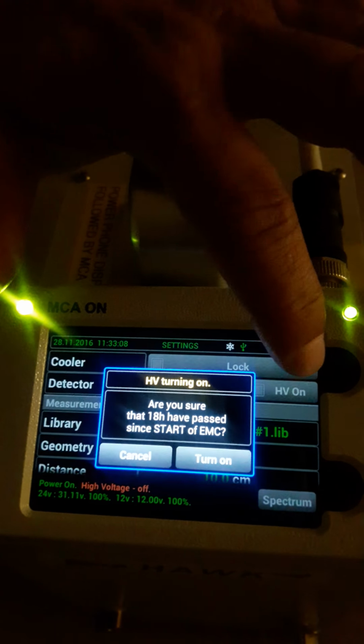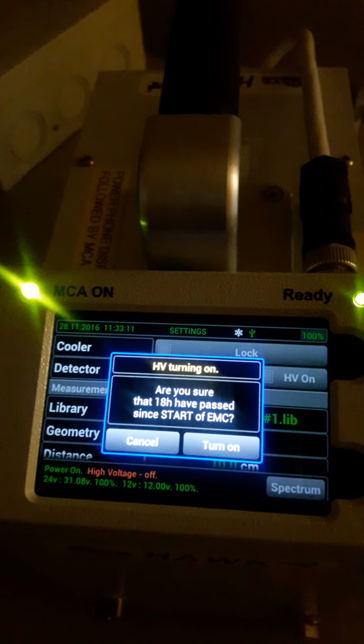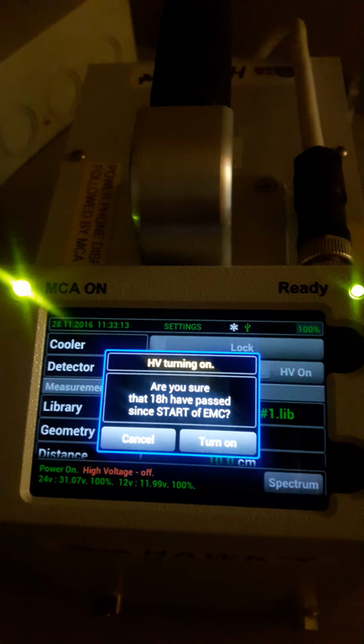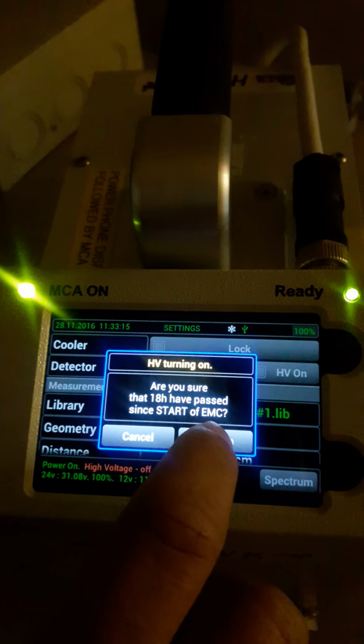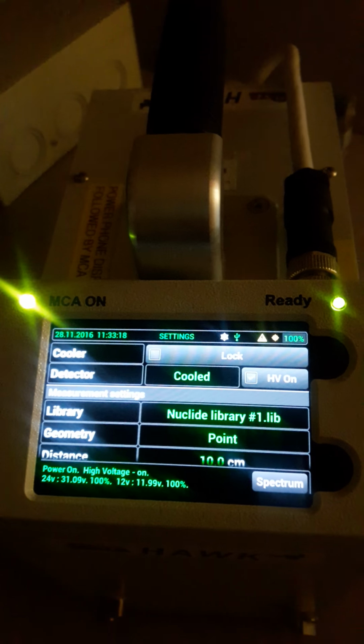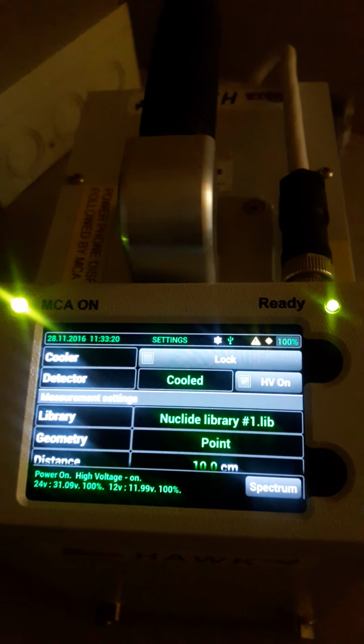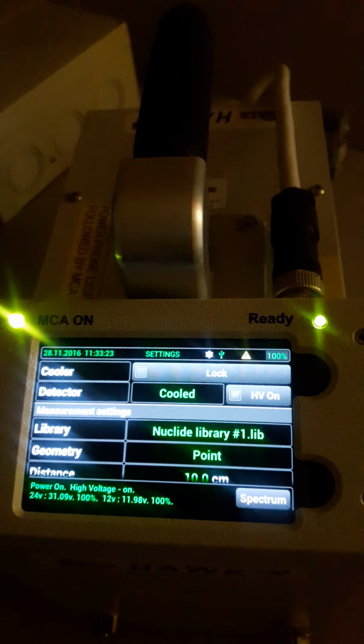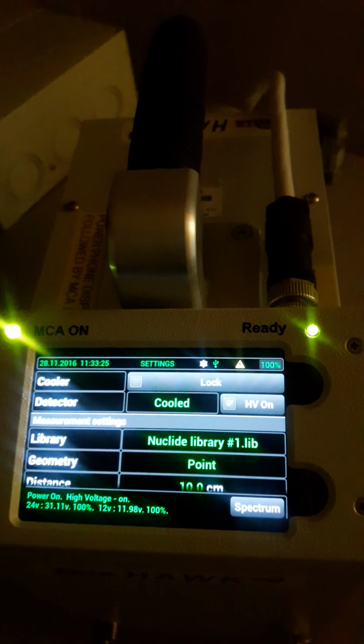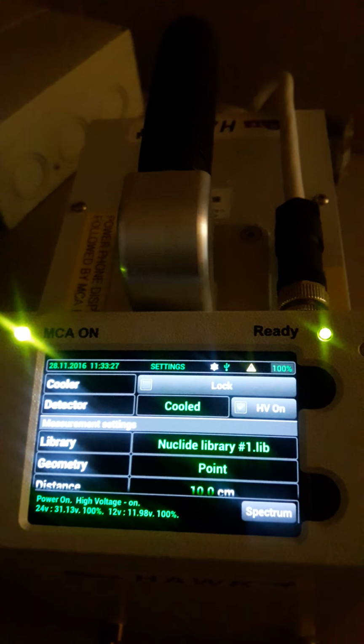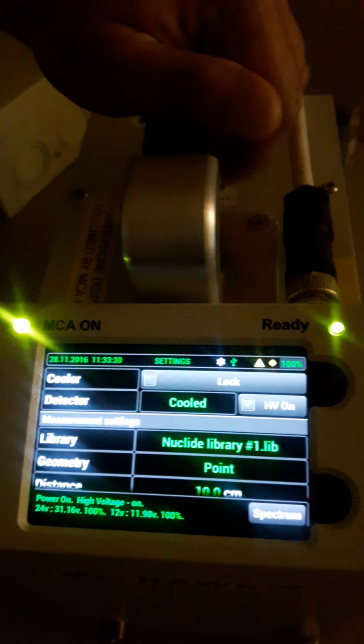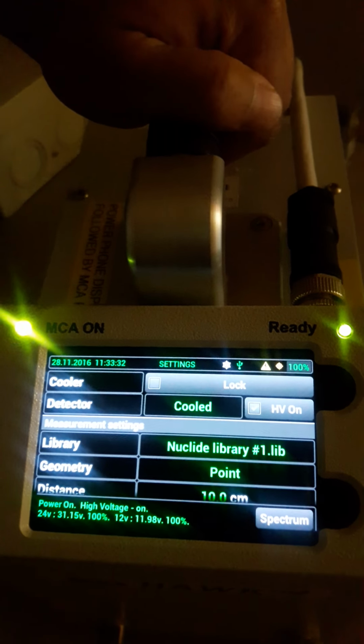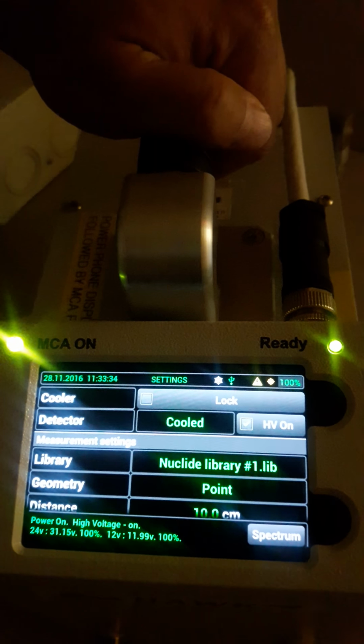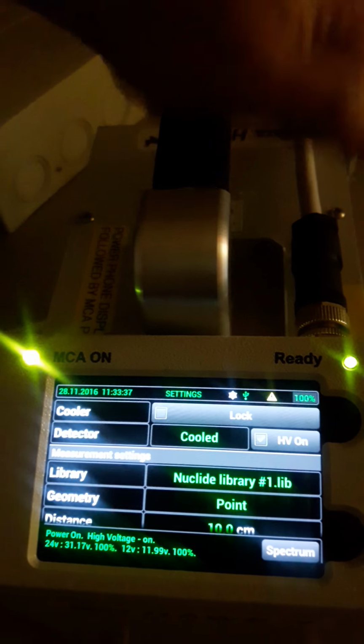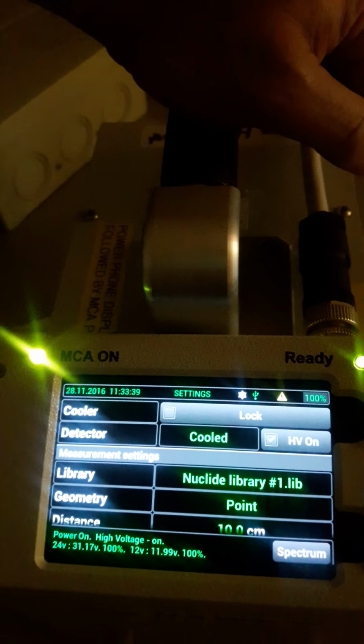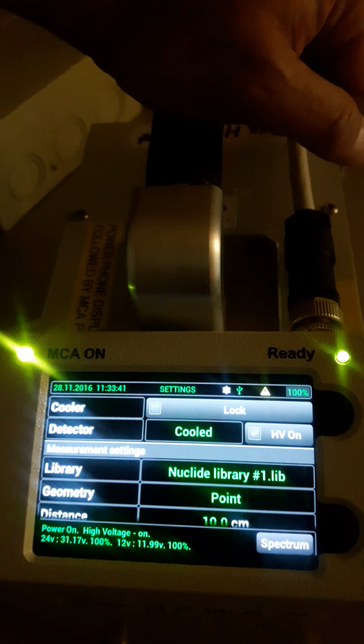So what I'll do is just simply select high voltage, and it's going to tell you, are you sure that you've cooled this system for about 18 hours? We'll say yes, I have. So we turn it on, and we have to give it a few seconds just for the high voltage to ramp up. So if there is a delay when you turn the high voltage on and off, just be patient with it for 10-20 seconds, because we have a safety mechanism in here that allows you to turn on the high voltage and not shock the detector. So right now my high voltage is on.